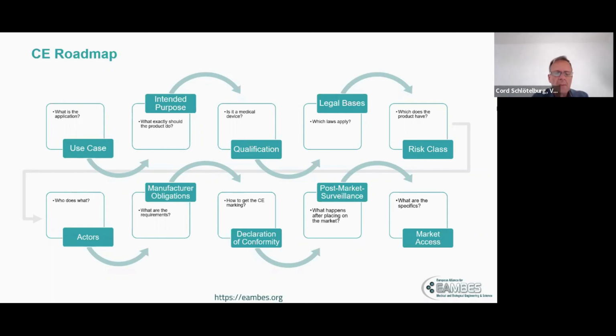the catalog, if you want, comes with the, let's say, typical obligations for a medical device manufacturer, which are mostly given in Article 10 of the MDR. It's like, for example, you need a quality management system, you need a risk management system, you must perform the clinical evaluation, you need the technical documentation, you have to fulfill all the registration tasks. You need instructions for use, and you need proper labeling of your device, and so on and so on. You have to fulfill it all, and in the end, you have to undergo a process of a conformity declaration in order to affix the CE mark onto your device.